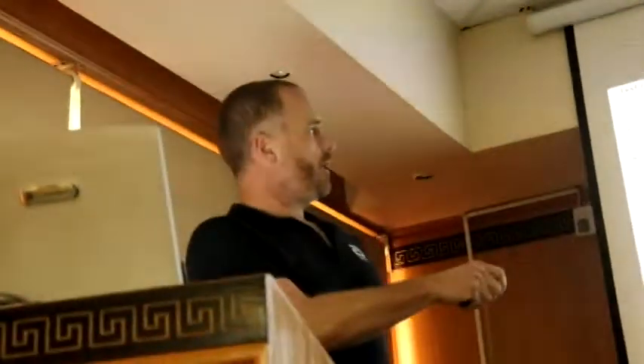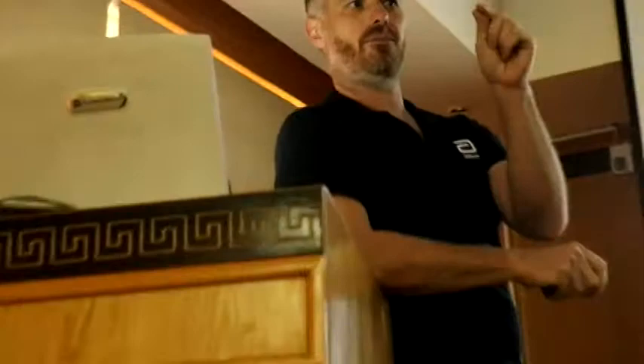Anyway, we've got a small R wave. We've also got an alert, and the alert says SecureSense is on. SecureSense is an algorithm in our device. It's probably my favourite algorithm, so we'll come on to that in a minute. SecureSense is on, and it detected non-sustained RV oversensing. What does that mean? That means it's picked up some extra signals on the tip ring electrode. So tip ring has detected some additional signals.